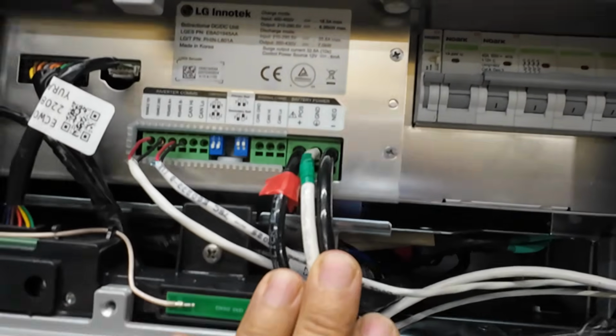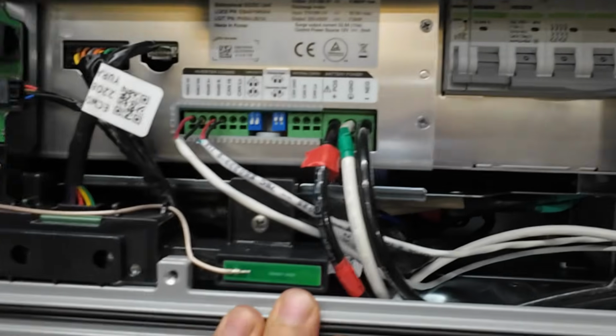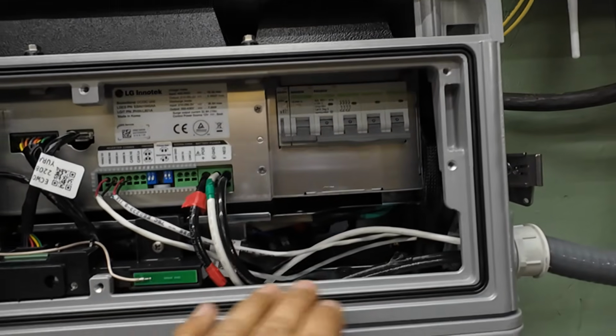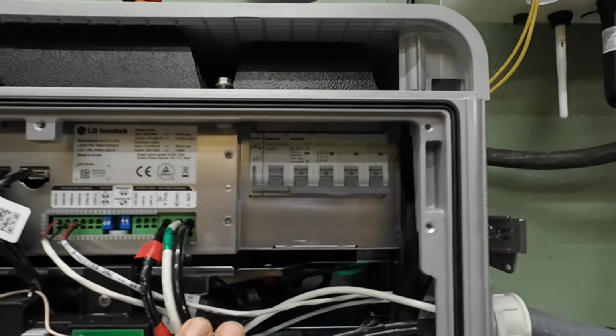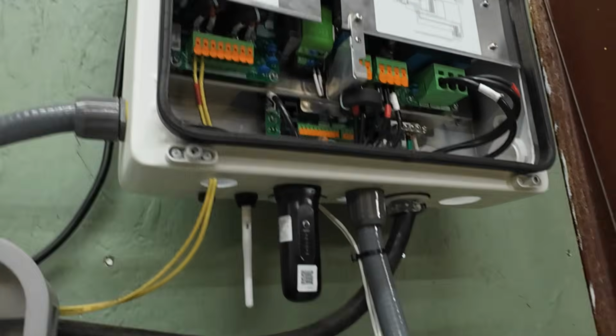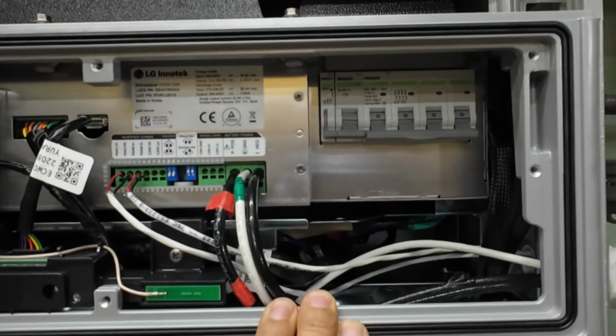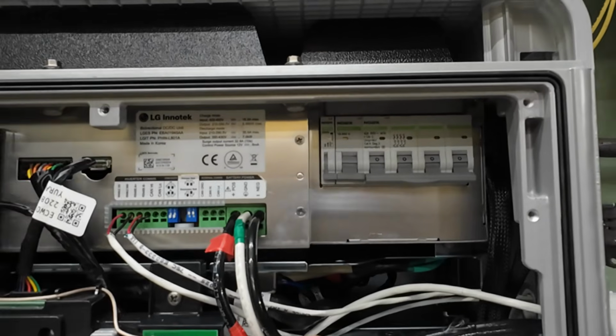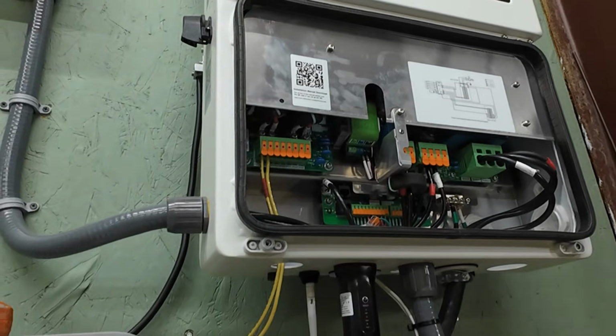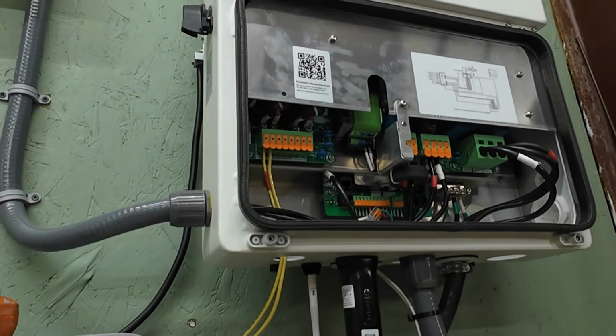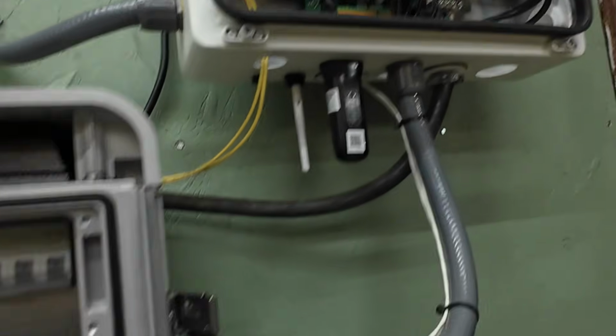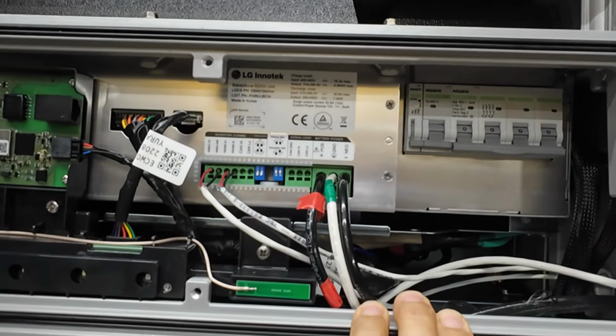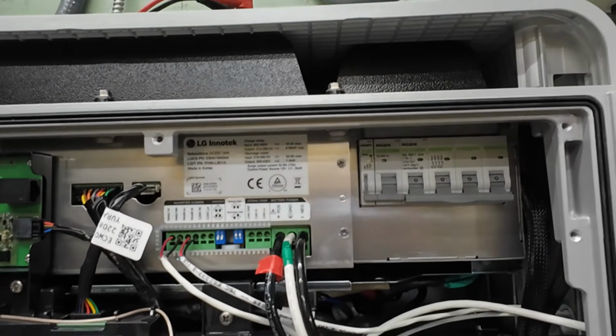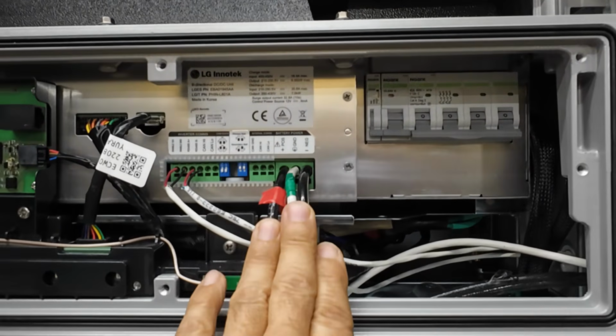So when you're hooking things up, you want to have the circuit breaker off, do all your connections up to the inverter, and then after your connections are done, you can turn everything on. When the inverter turns on, it sends the signal to the battery to activate the contactor, and then you've got high voltage coming out of here.